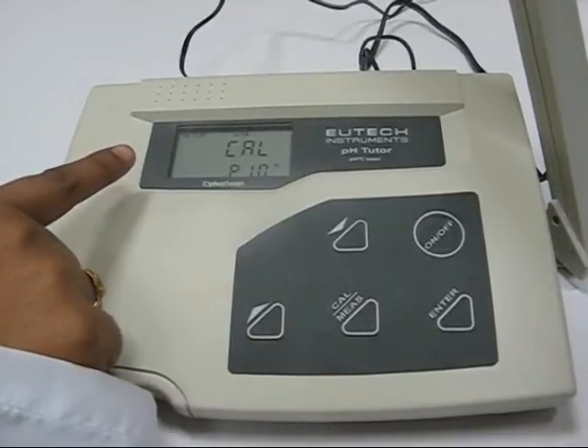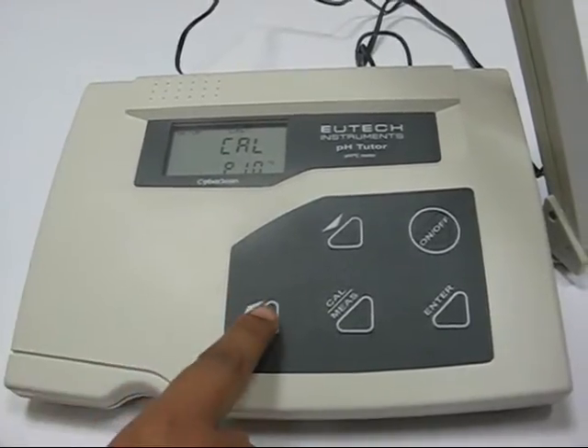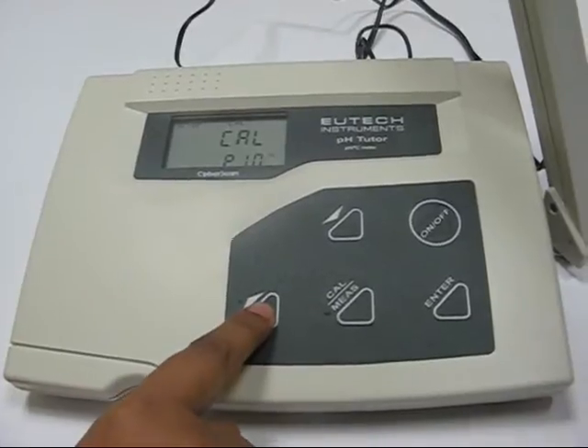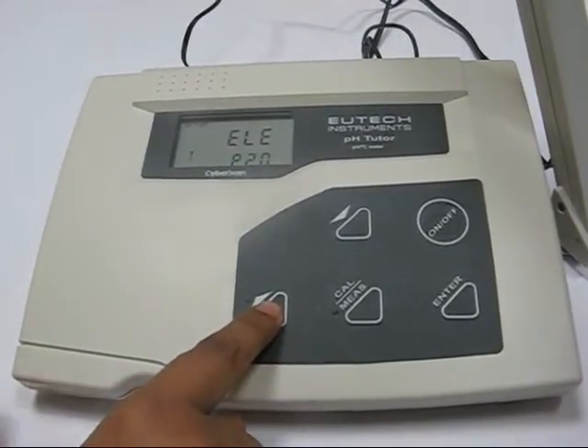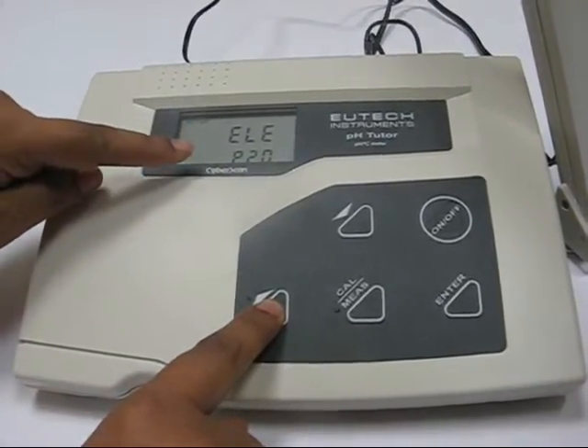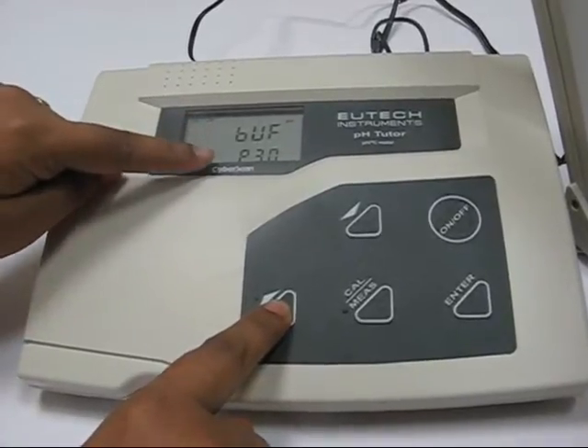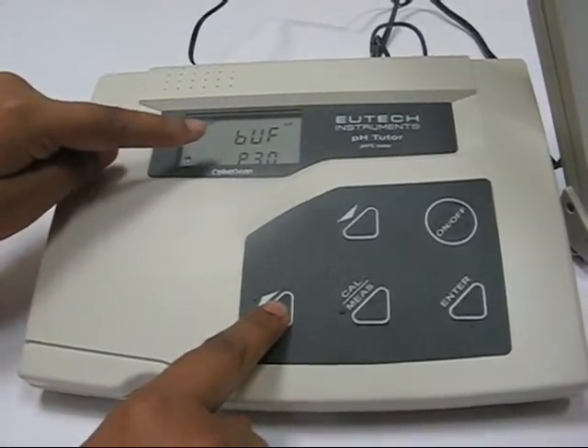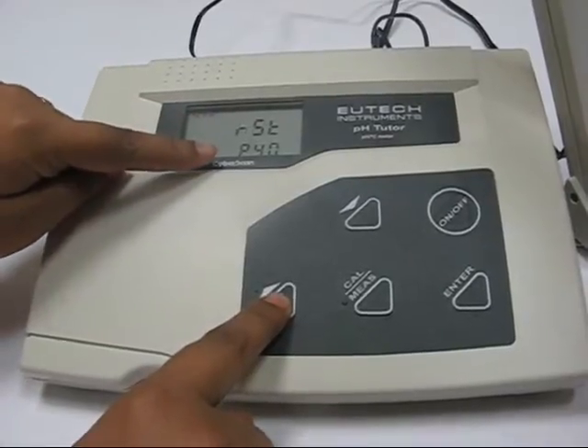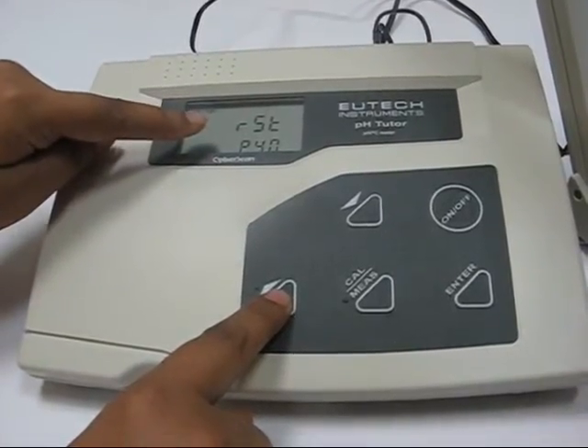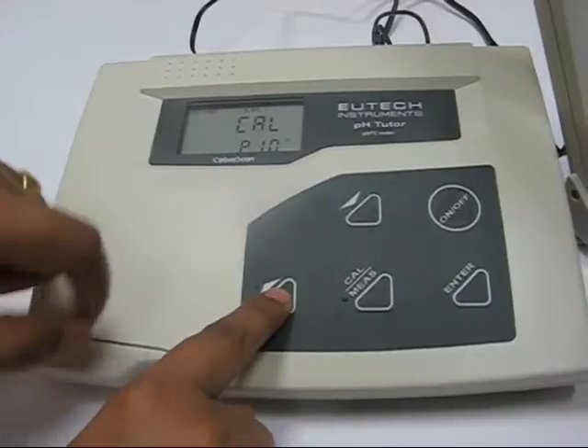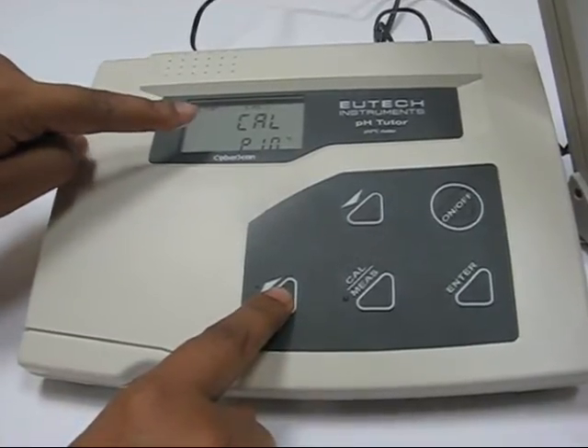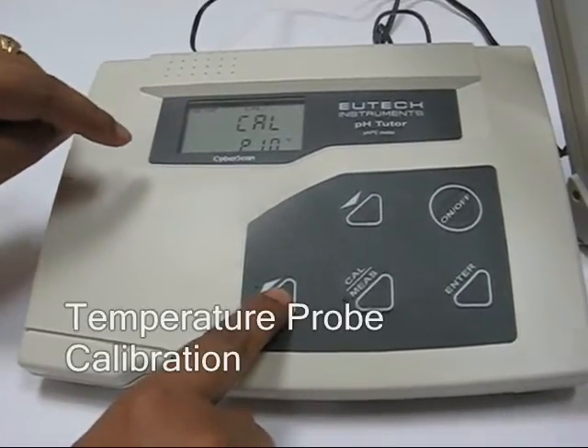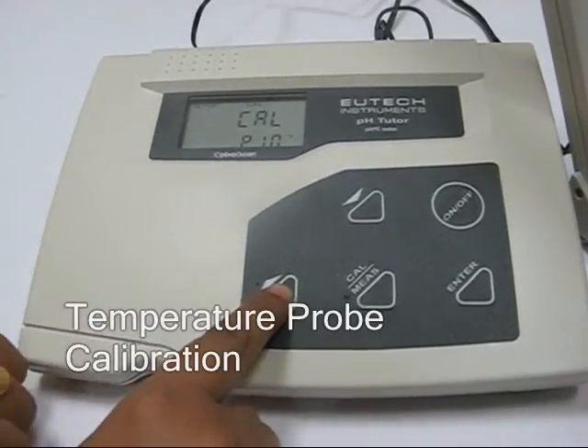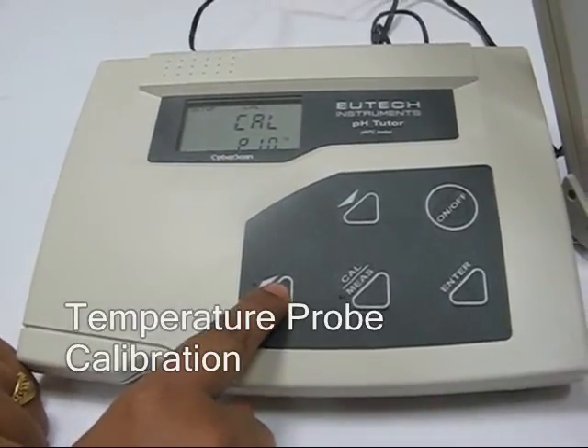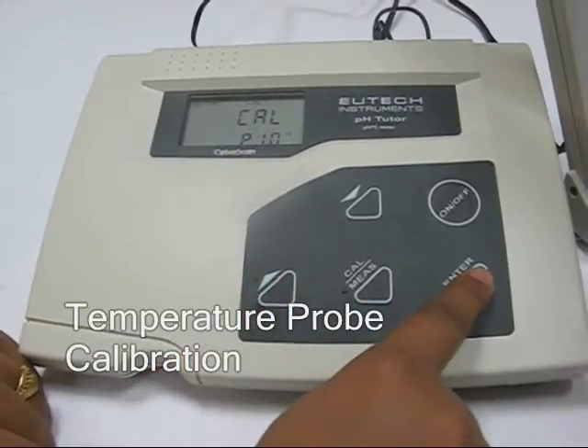Let's now press the increment or the up arrow key to toggle through the menus. You go to 2, which is electrode, ELE, press again. You will go to 3, which is BUF for buffer selection, and once more 4.0, which is RST, which stands for reset. Press the up key again, we'll go to 1.0. Now this menu is the one that you need to use for calibrating the temperature probe if you have connected a temperature probe to the unit. How do you do this? Press the enter key now.